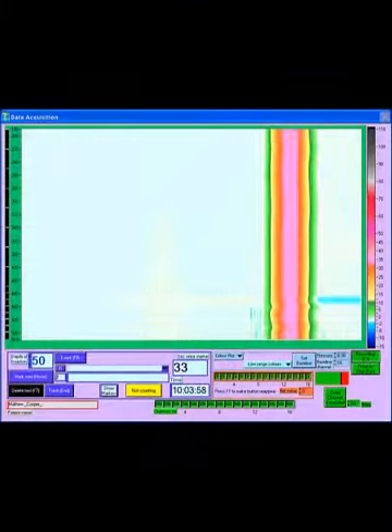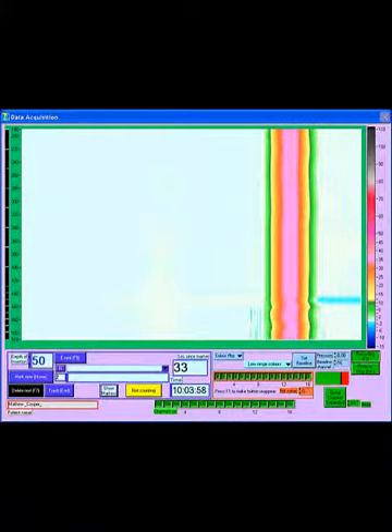In order to check that each channel is recording and that the calibrations are consistent between channels, lift up the bowl containing the catheter. This should cause a vertical stripe in the recording, which should be consistent across channels. If one channel does not rise with the others, there is likely to be a problem with the perfusion of that channel, and it will need to be investigated. If you see a picture similar to that on the screen, you are ready to start the study.